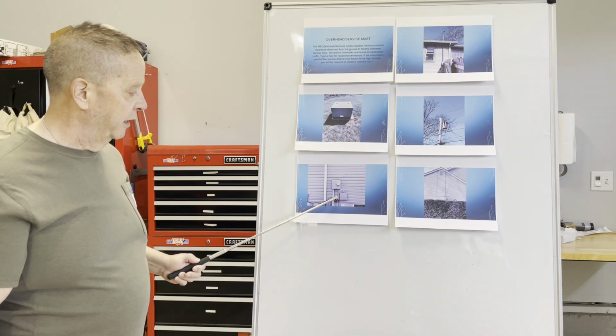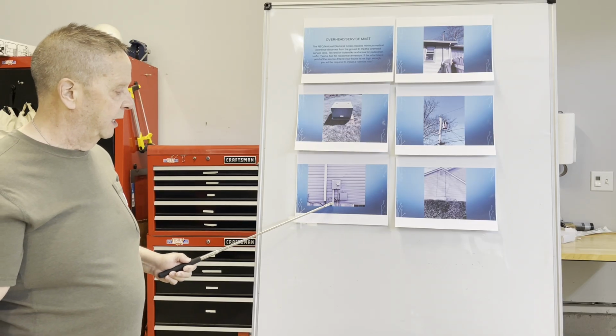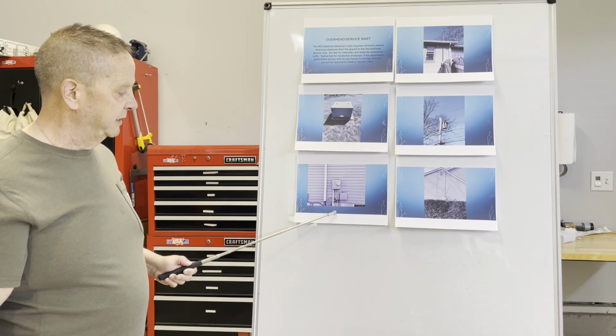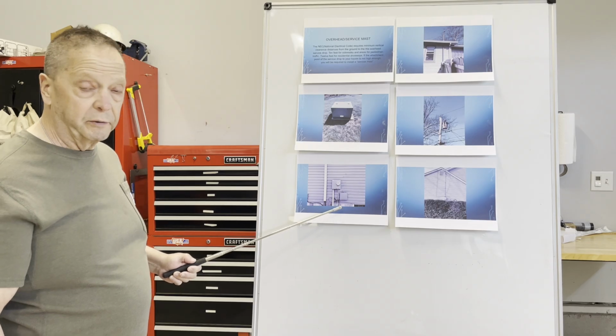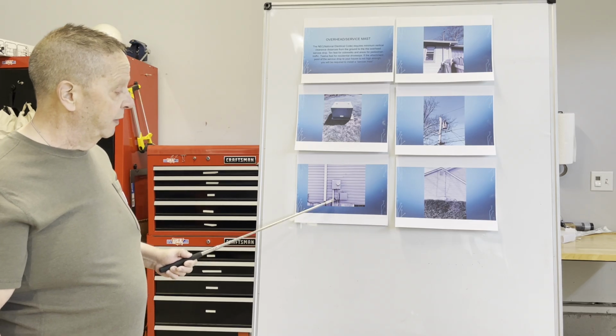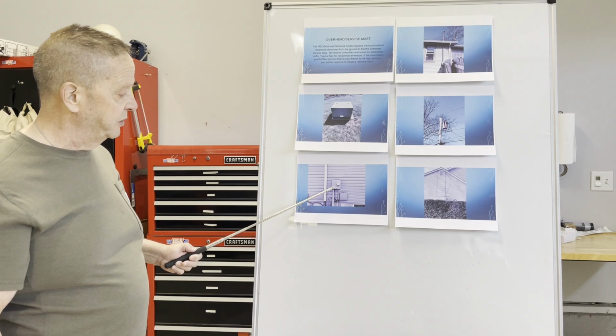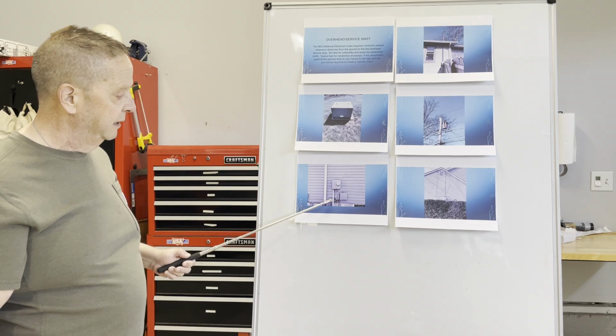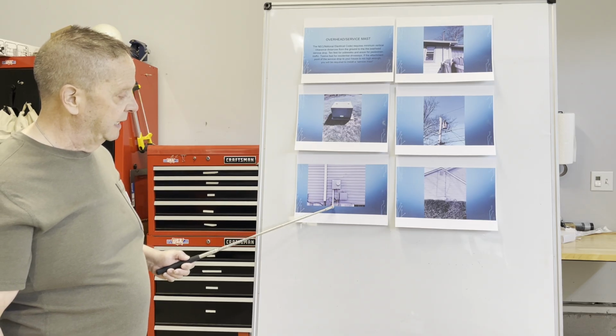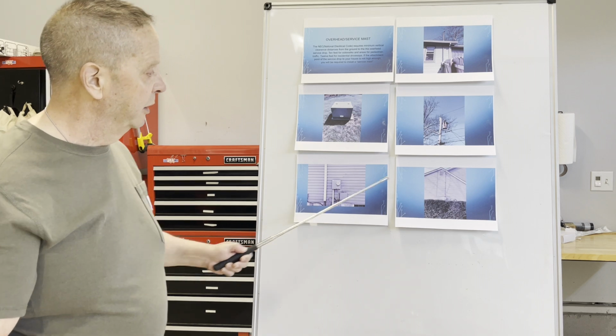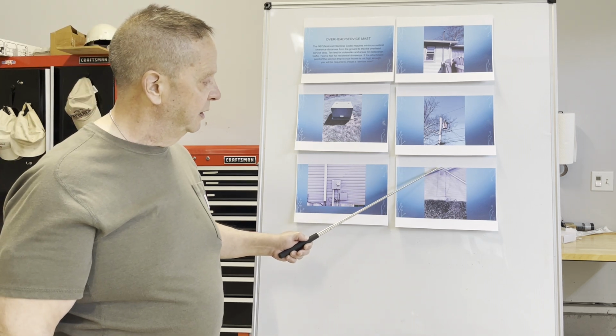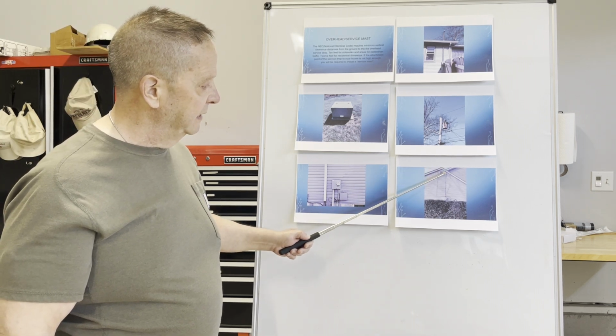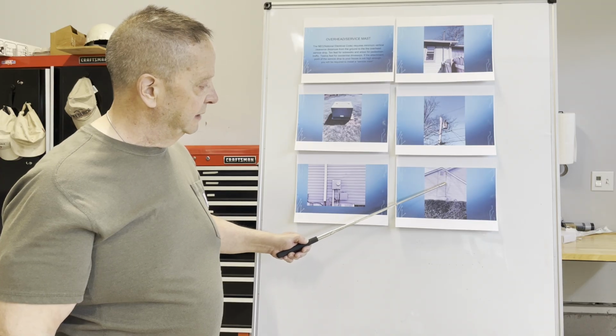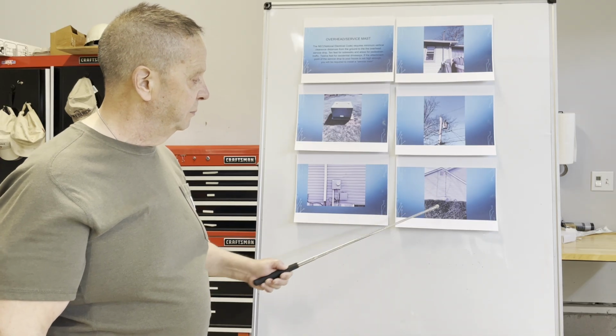Here you can see an underground service that has underground direct burial cable that comes underground. And then this is a piece of PVC that goes into the ground at least 18 inches, and that's for physical protection. Here you can see an overhead service that comes to the house, and then the SE cable is run down into the top of the meter pan.